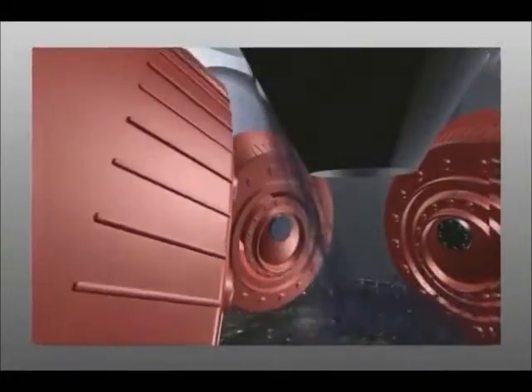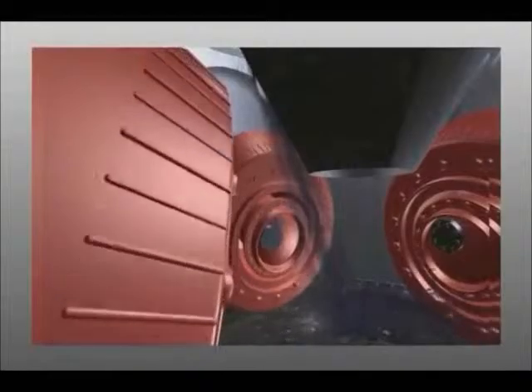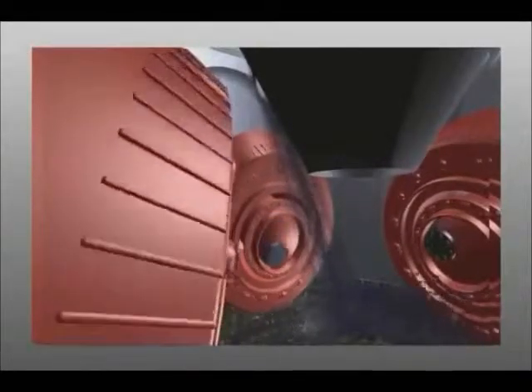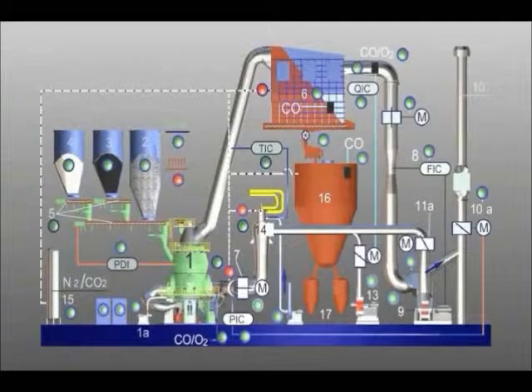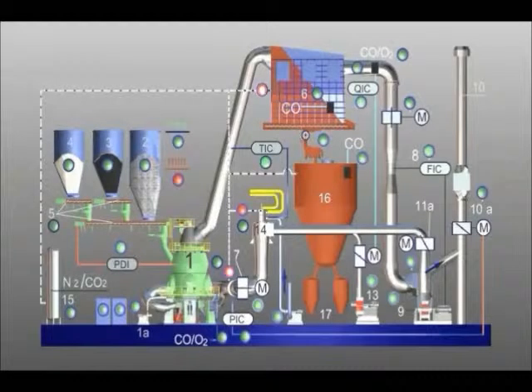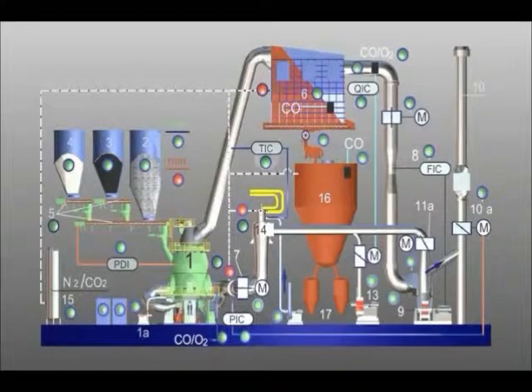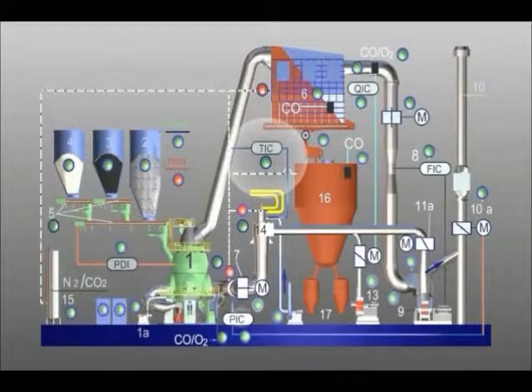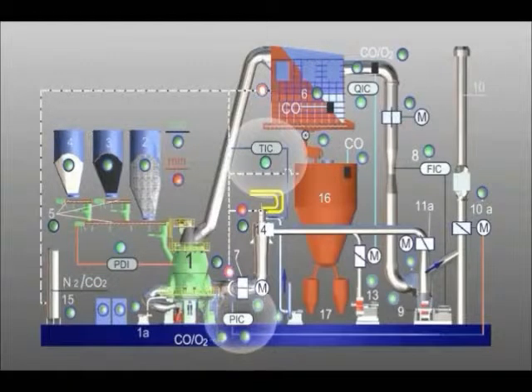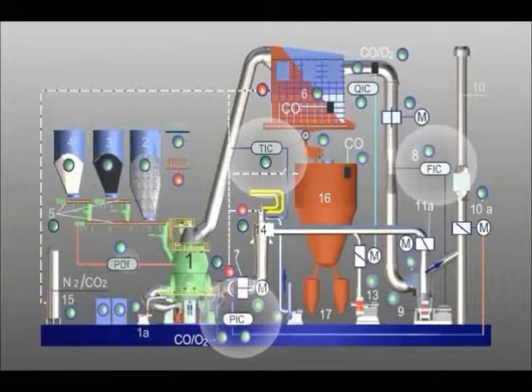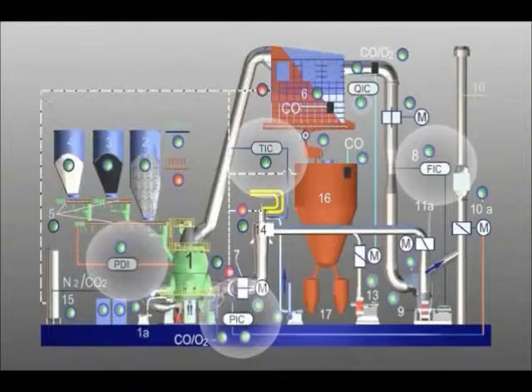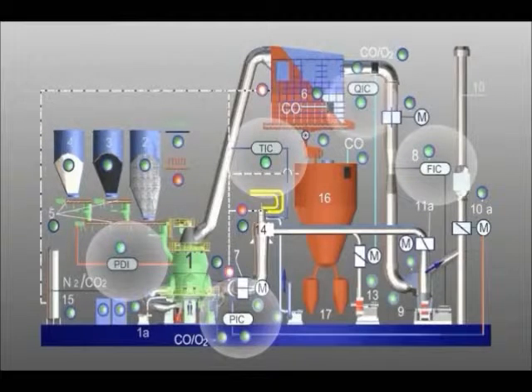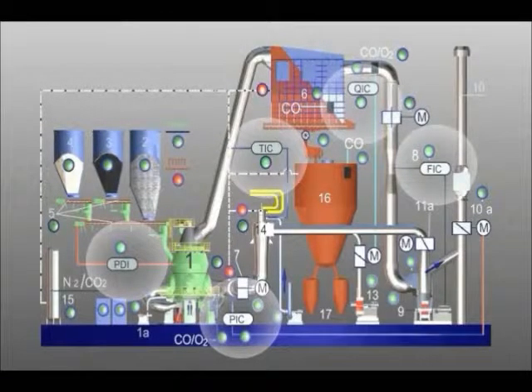The material feed is set to the minimum throughput rate of 40 percent. All controllers and the associated controlled systems are set to automatic: TIC after mill, PIC before mill, FIC after filter, PDI mill differential pressure, QIC oxygen control after filter.